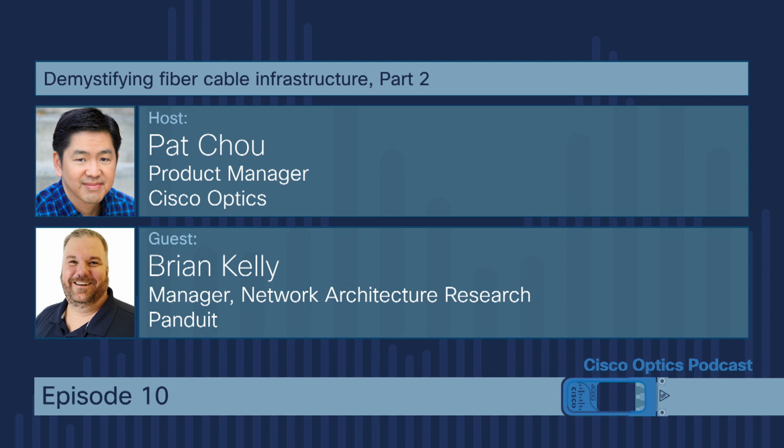A lot of times people don't realize that when you have, say, 35 or 40 of these cables running in your cabinet, it puts a tremendous amount of stress on the cable management fingers that you may have in your cabinet, because the weight of these cables is a lot more than you're generally used to with, say, RJ45 twisted pair connectivity. I see, hadn't thought of that. And fiber obviously is very, very light. The AOCs are a little bit heavier than a fiber patch cord, but not bad. So you really don't have both the rigidity and the weight issue that you might have with direct attach copper.